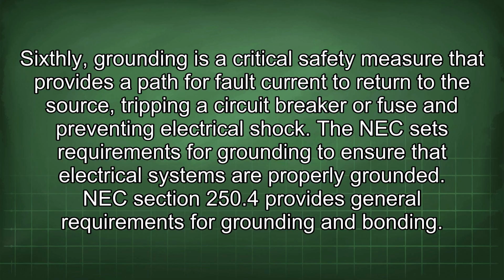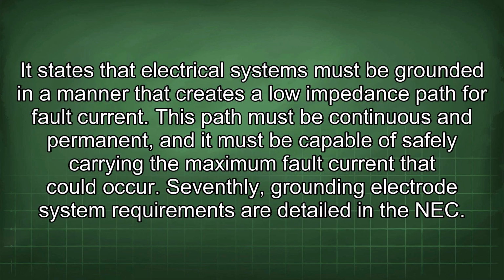NEC Section 250.4 provides general requirements for grounding and bonding. It states that electrical systems must be grounded in a manner that creates a low impedance path for fault current. This path must be continuous and permanent, and it must be capable of safely carrying the maximum fault current that could occur. Seventhly, grounding electrode system requirements are detailed in the NEC.